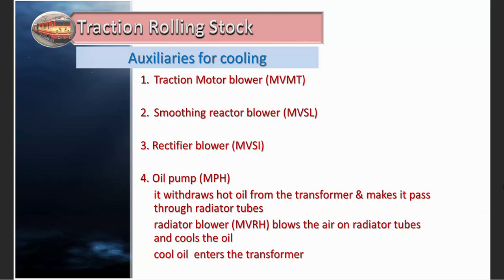It then makes the oil pass through the radiator tubes. On top of the radiator tubes, we blow air through the radiator blower, and in the process the transformer oil gets cooled. After that, the oil is pushed back into the transformer. So this cycle remains in service throughout the journey, and we keep on rotating the transformer oil using the oil pump.